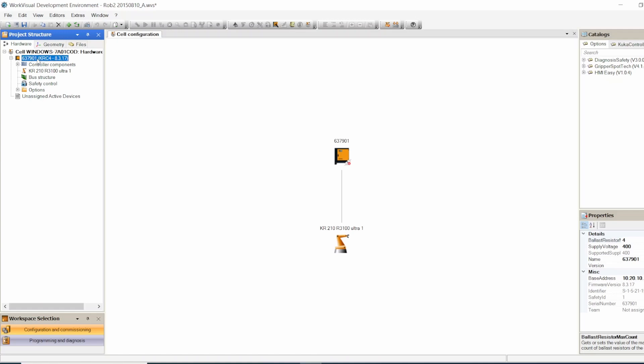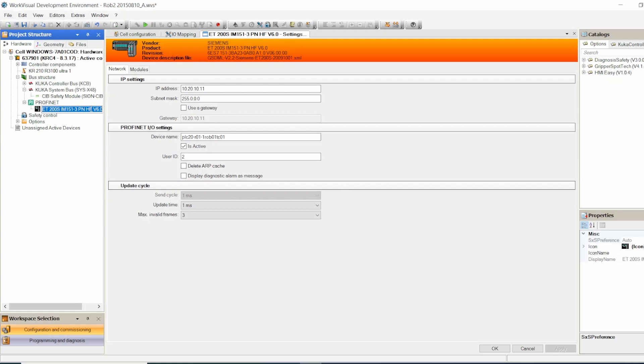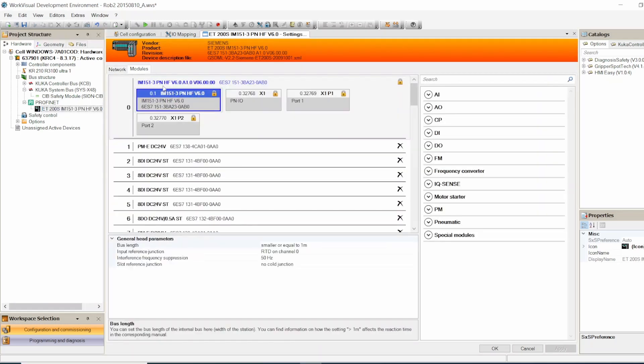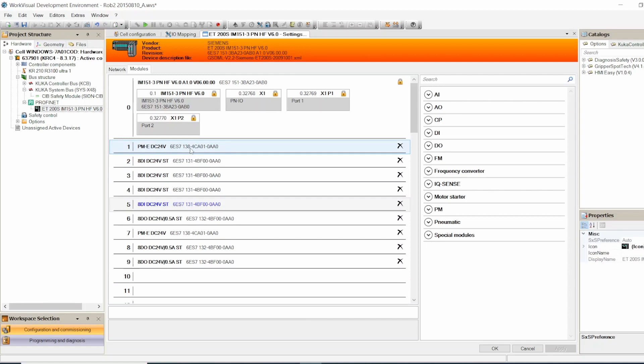If we want to see the configuration we did, double click on the controller to open it. Here it shows the Profinet communication and the ET200 right here. If I double click on it and look at the modules, we see all the modules that we added to the KUKA. The ET200 has a power module, then four digital inputs, one digital output, another power module, and then two outputs.